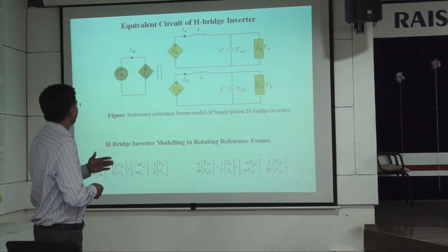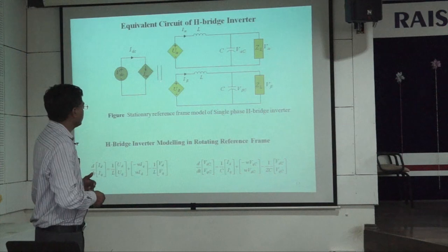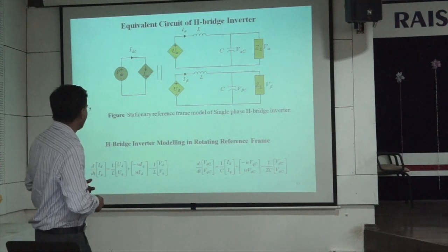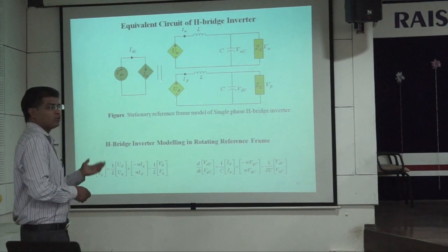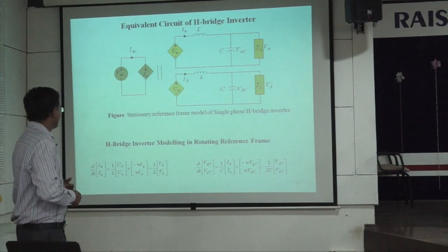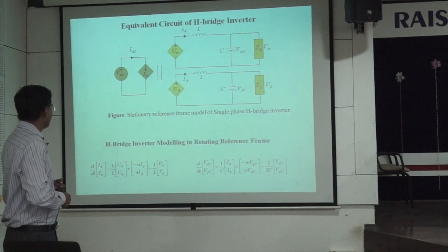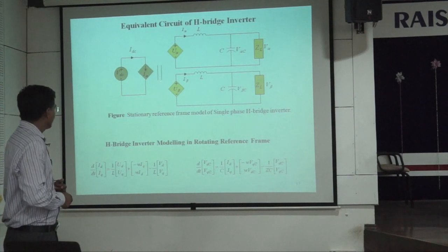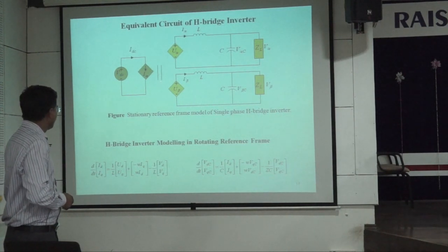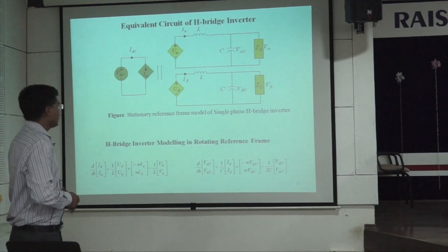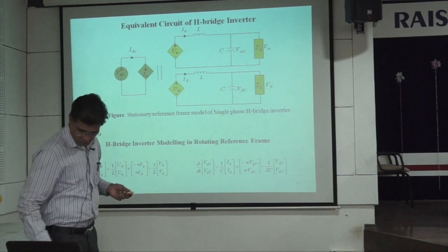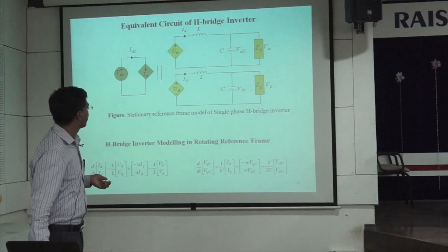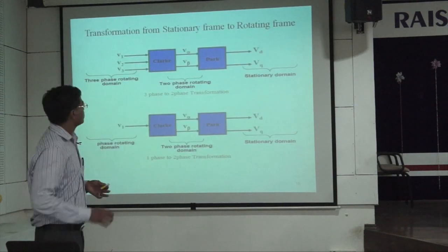There is also a model in the rotating reference frame. When I modeled in the rotating reference frame, I used the chain rule, and I came to the conclusion that the D component current has an effect on the Q component current, and the Q component has an effect on the D component current. So that's why we have to decouple both these components for the effective control of the device.